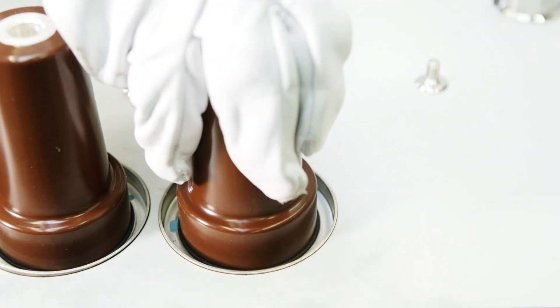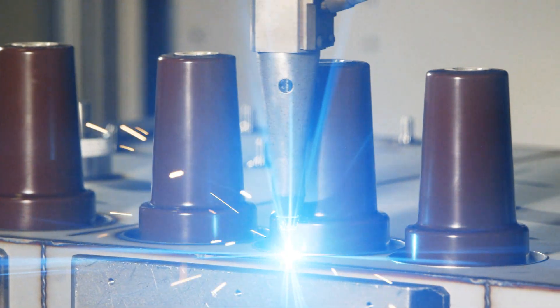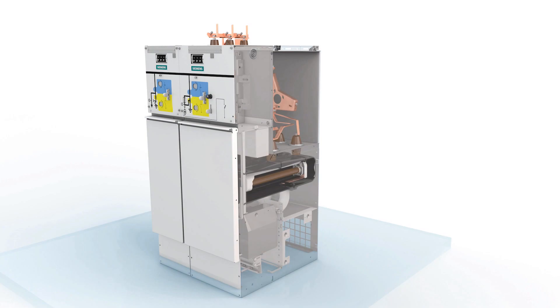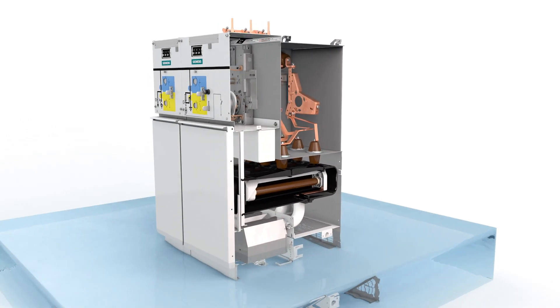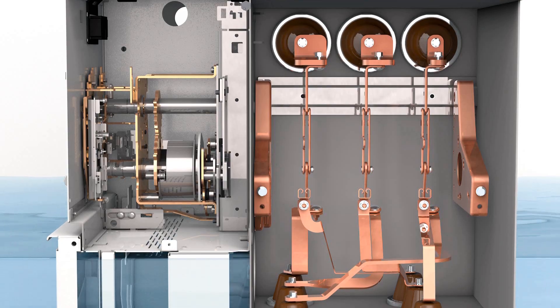A consistently reliable hermetic enclosure is provided by Siemens-produced cast resin bushings, jointly welded with stainless steel plates, ensuring high precision and mechanical resistance. This prevents parts under high voltage in the main circuit from coming into contact with any water which may have entered the system.